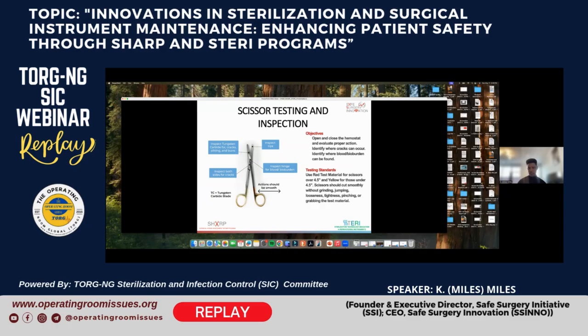So it's not the surgeon who's telling the OR nurse, this instrument isn't cutting. A lot of times we find ourselves in situations where we have instruments that are not functioning properly. The surgeon complains about it, hands it over to the nurse, and then nothing else happens, because no one knows how to properly inspect the instruments, and no one can go back and say, okay, based off WHO guidelines, based off the IFUs of the manufacturer, these are the inspection points. These are the things that are wrong with it, and it's not safe to use.